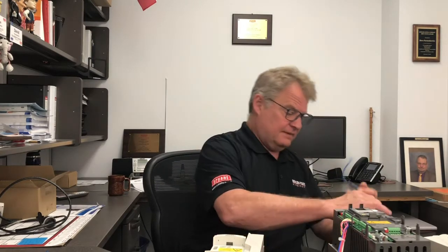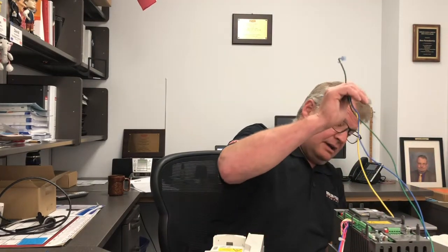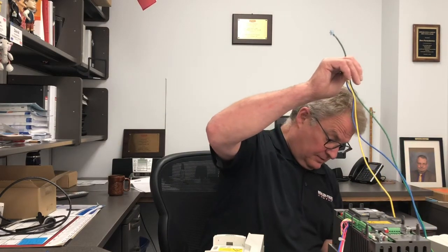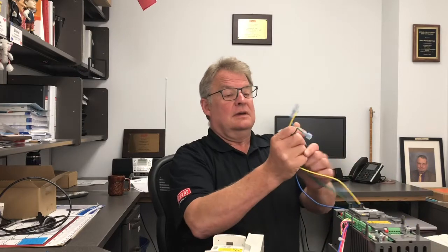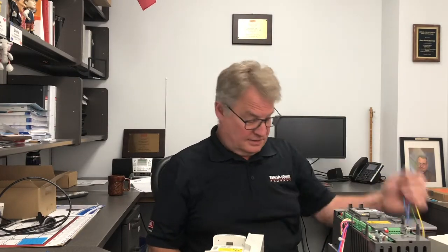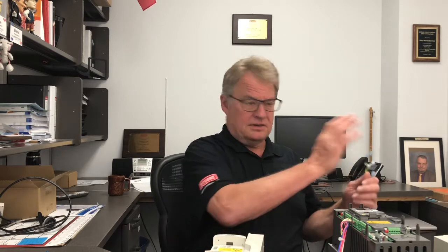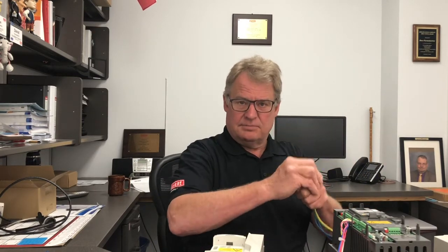If I look at the wiring, you can see right here, this is the wiring that would be going to the motor, and there are factory spade connectors on it. The wiring from the control box also has factory spade connectors. So I can take the power from the control box, unplug it from this, take the motor on the other end, unplug it from this, and just plug them together and bypass the drive.